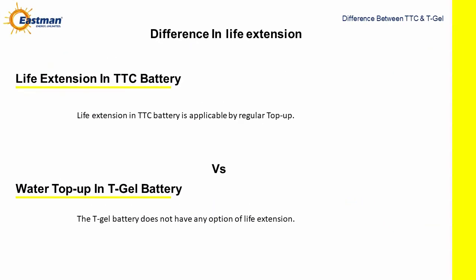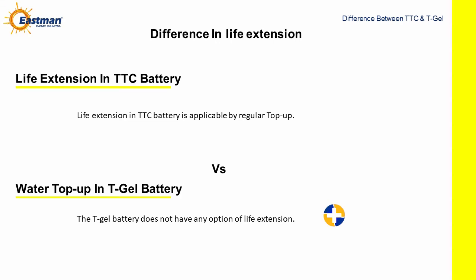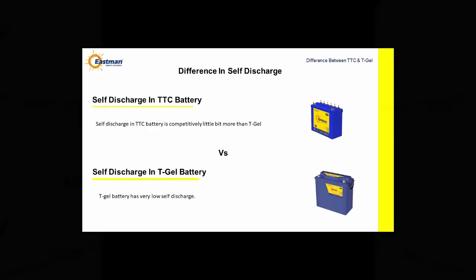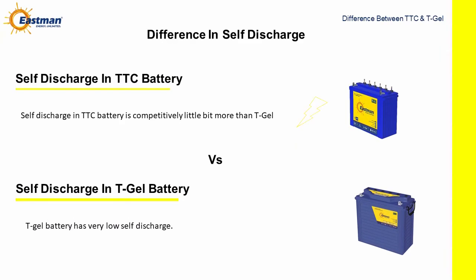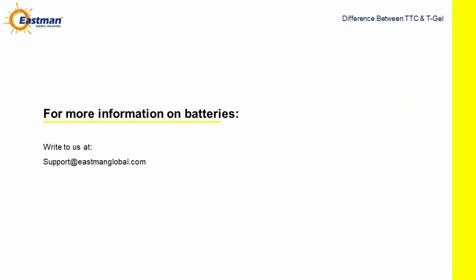Difference in life extension. Life extension in TTC battery is applicable by regular top up. The T-Gel battery does not have any option of life extension. Difference in self-discharge. Self-discharge in TTC battery is comparatively a little bit more than T-Gel. T-Gel battery has a very low self-discharge. For more information on batteries, write to us at support@eastmanglobal.com.